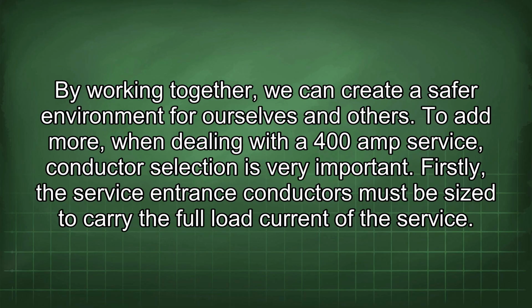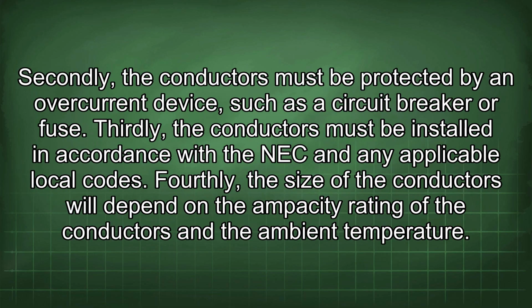To add more, when dealing with a 400 amp service, conductor selection is very important. Firstly, the service entrance conductors must be sized to carry the full load current of the service. Secondly, the conductors must be protected by an overcurrent device, such as a circuit breaker or fuse. Thirdly, the conductors must be installed in accordance with the NEC and any applicable local codes. Fourthly, the size of the conductors will depend on the ampacity rating of the conductors and the ambient temperature.